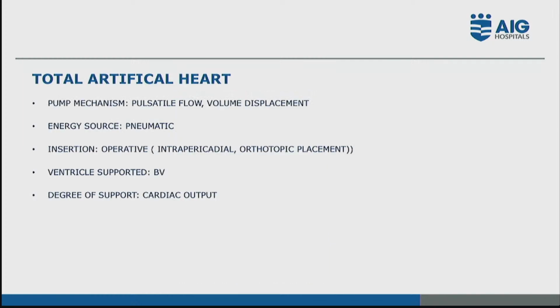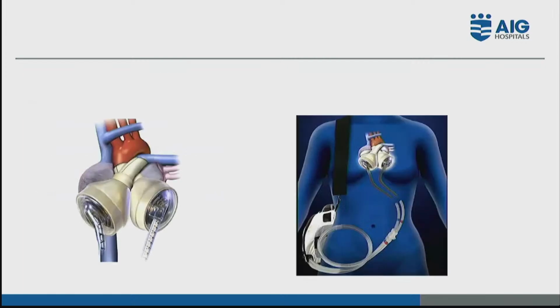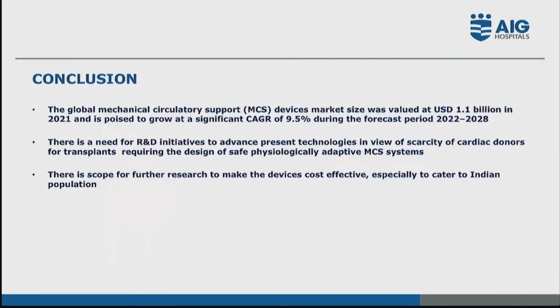So the last in this is the total artificial heart. In this, the pump mechanism has a pulsatile flow with volume displacement. It is implanted in an intrapericardial orthotopic placement. As you can see, both the ventricles are replaced by an artificial membrane, and with pneumatic pulsation, the blood is pumped into the great arteries directly. There are two types of total artificial heart commercially available in the market right now, but these are quite expensive. So in the Indian market, it has not yet picked up that much.